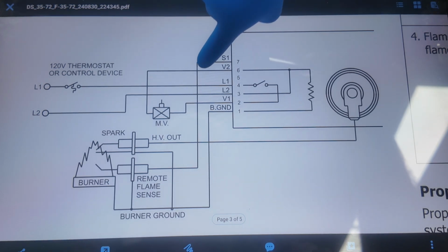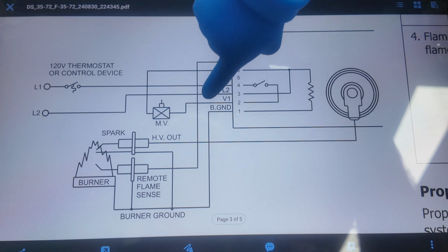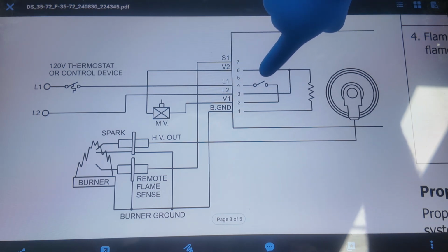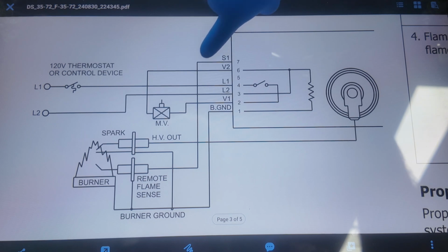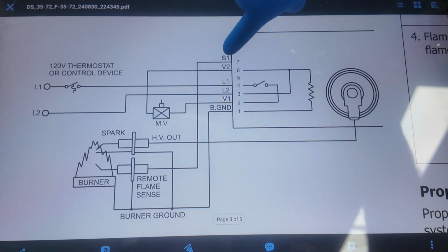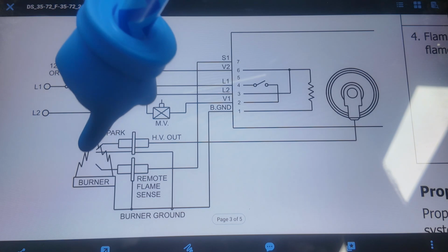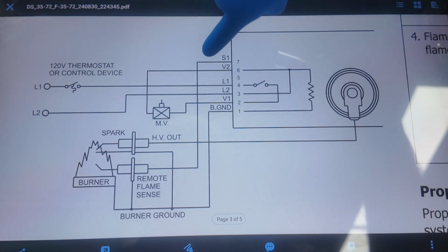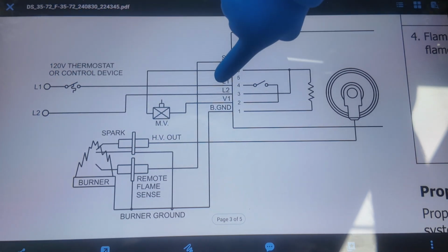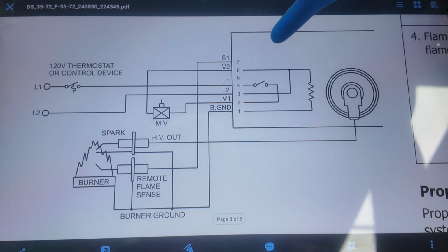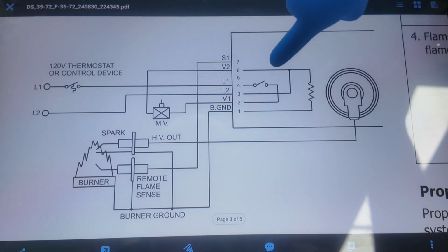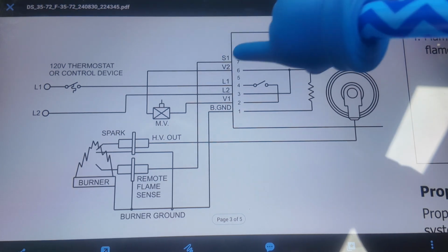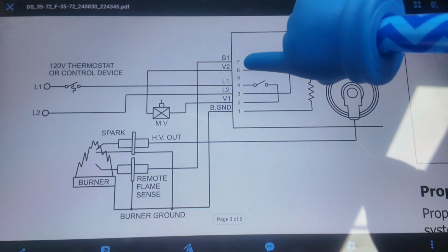If you don't get any electric out V1 after the ignition time is complete, S1 is your sensor. If this sensor wire or probe is grounded out at all, meaning damp dirt on it, cracked porcelain, a wire rubbing somewhere, mice chewed on a wire, if that wire is shorted out anywhere, you put power to L1 and L2 and it will not put power out V1 and V2. If S1 is shorted to ground at all, you will get 0 voltage out V1.